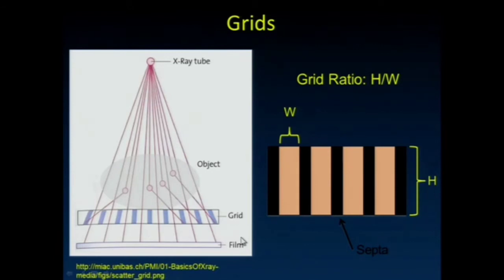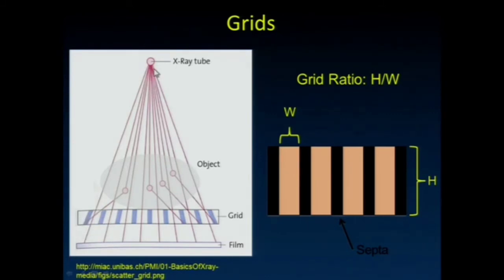Grids are another way to reduce scatter, and they're very similar to the collimator used in nuclear medicine. In nuclear medicine, the collimator focuses gamma-ray energy onto the camera. Here, we use the grid to reject scatter—the holes are lined up at a particular distance and angle to the x-ray tube.